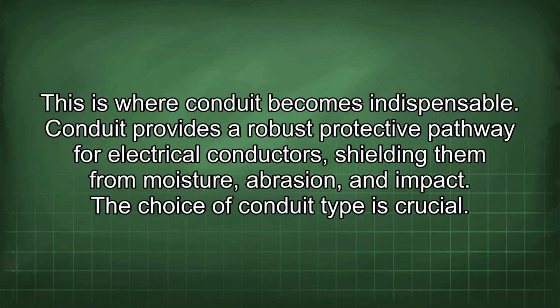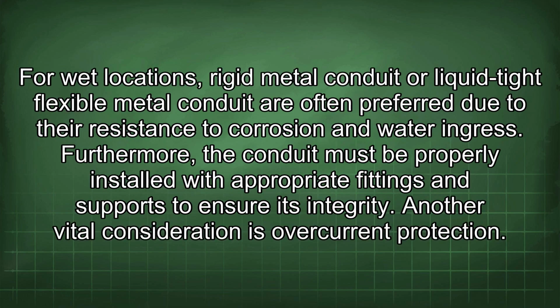Conduit provides a robust protective pathway for electrical conductors, shielding them from moisture, abrasion, and impact. The choice of conduit type is crucial. For wet locations, rigid metal conduit or liquid-tight flexible metal conduit are often preferred due to their resistance to corrosion and water ingress. Furthermore, the conduit must be properly installed with appropriate fittings and supports to ensure its integrity.